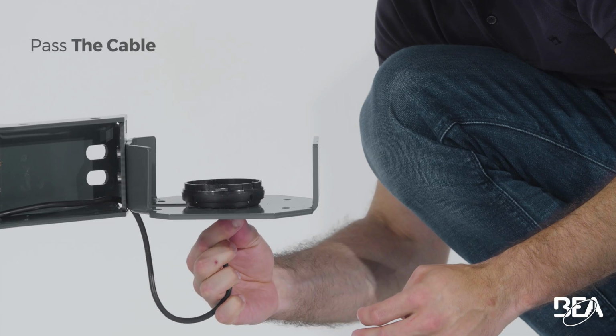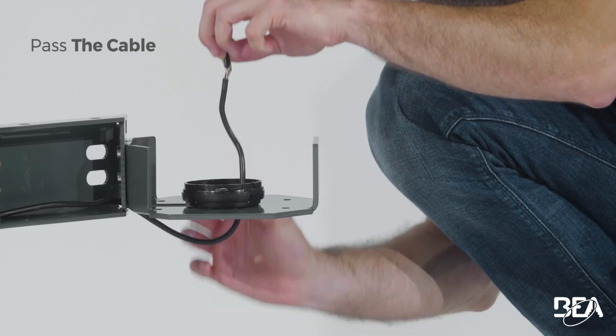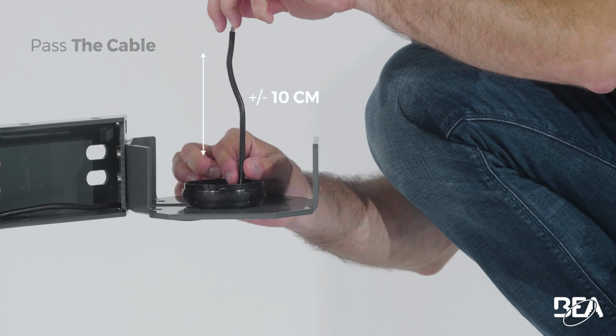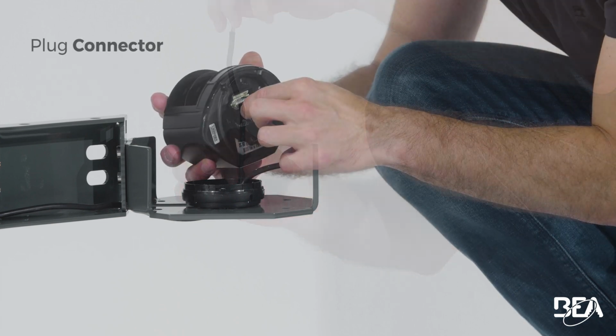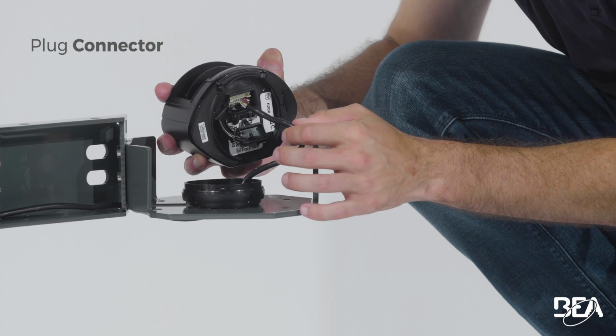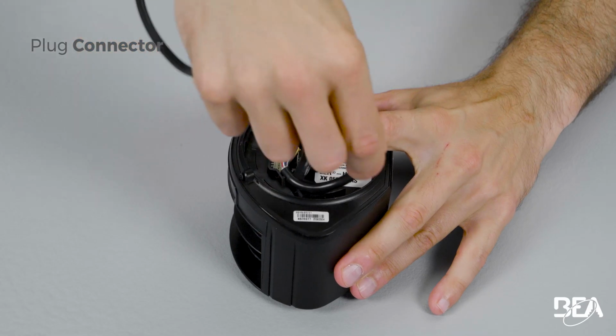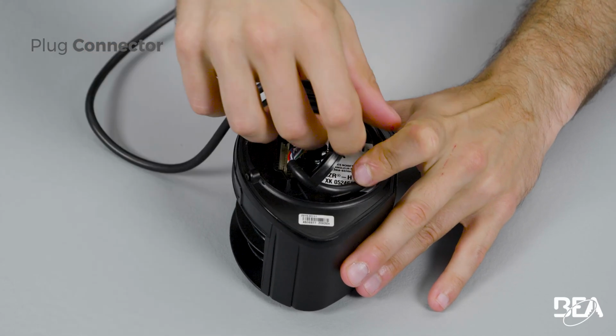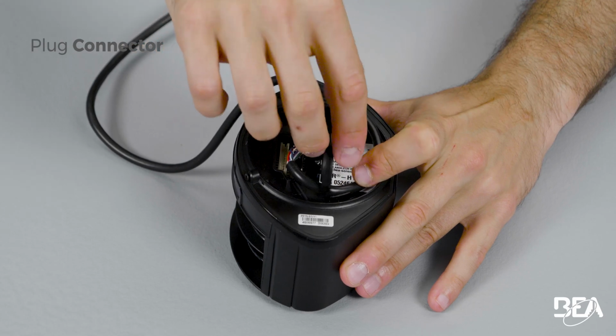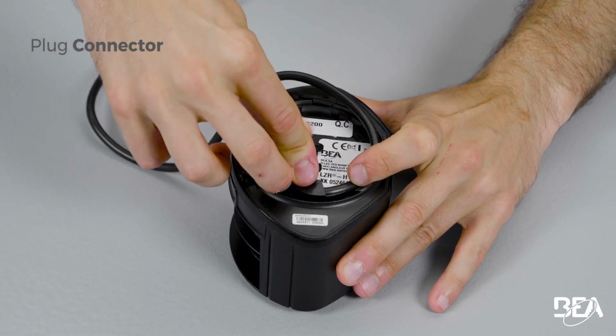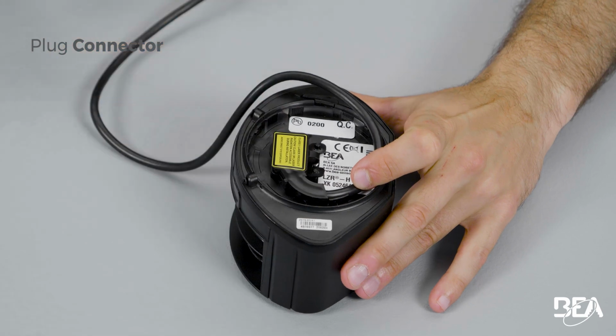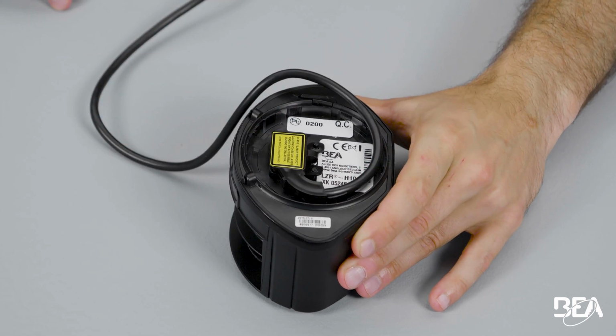Pass the cable and connector through the base, leaving 10 centimeters sticking out. Open the protective cap, plug the connector and position the cable in the slit. Close the protective cap and fasten it firmly. If not closed completely, the sensor cannot be positioned correctly on the bracket.